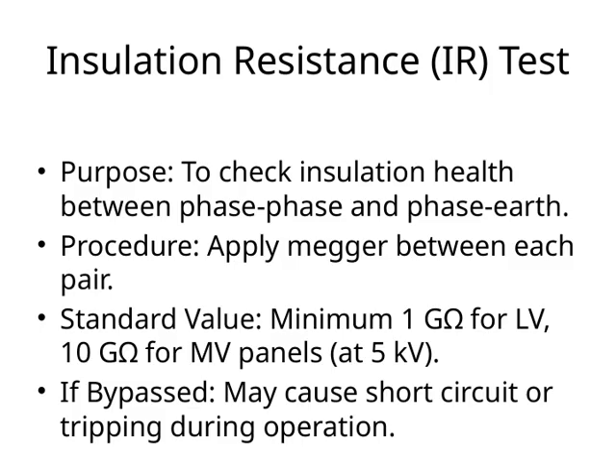Now, regarding the standard values for low voltage panels, we look for a minimum of 1 gigaohm and for medium voltage panels at 10 gigaohms when testing at 5 kilovolts. These numbers help us determine if the insulation is in good condition. It's important to note that if the insulation test is bypassed, it could lead to serious problems, like short circuits or tripping during operation. That's why thorough testing is essential for safe and reliable system performance.